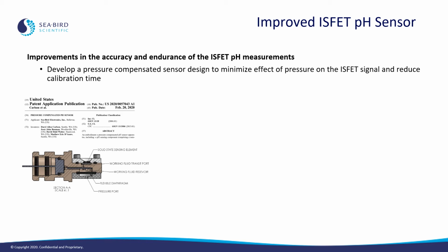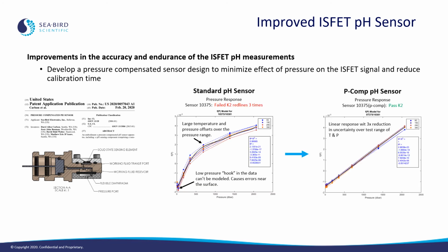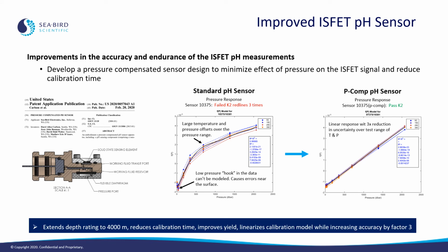So we've been looking at ways to minimize the effect of pressure on the actual ISFET signal, but also to reduce the calibration time. We recently submitted a patent for a pressure compensated design that removes the effect of pressure on the sensor. And what you can see is that the highly nonlinear response of a standard ISFET pH sensor gets completely linearized in this design. With that, we're able to extend the depth rating to about 4,000 meters. It reduces the calibration time, improves the yield, linearizes the calibration model, while actually increasing the accuracy by a factor of 3. So I think we're on the right track here.